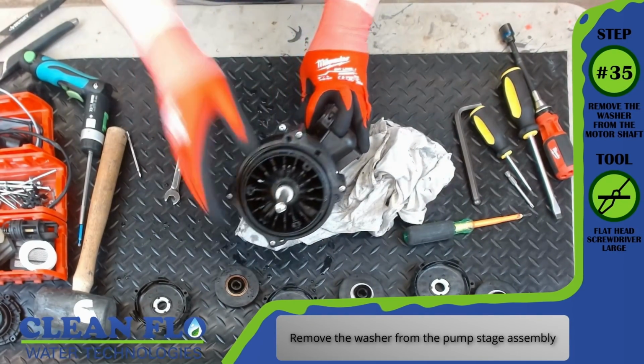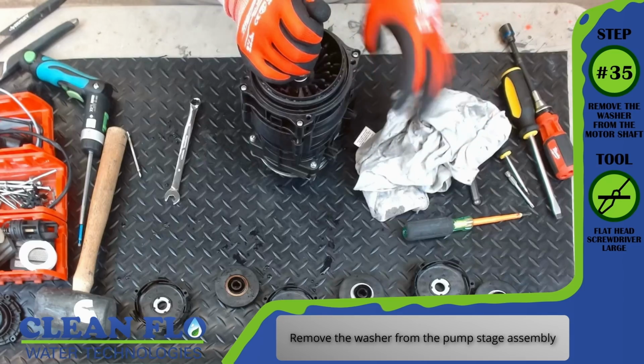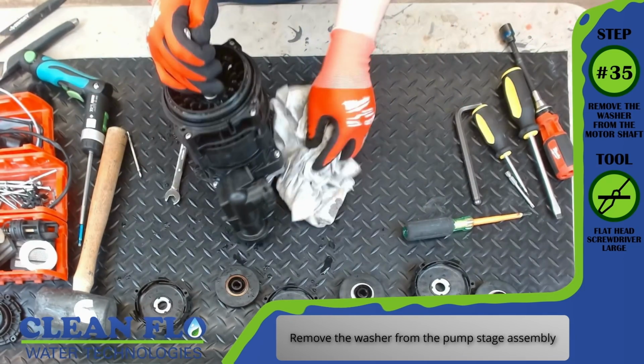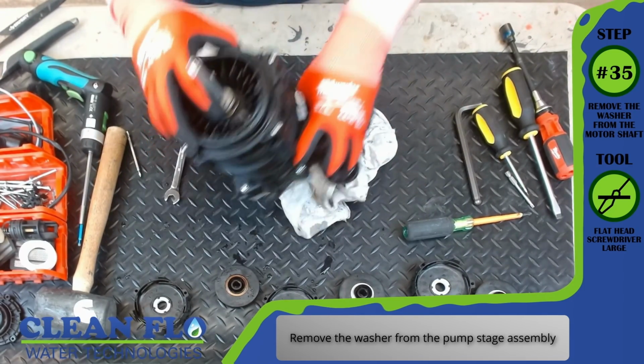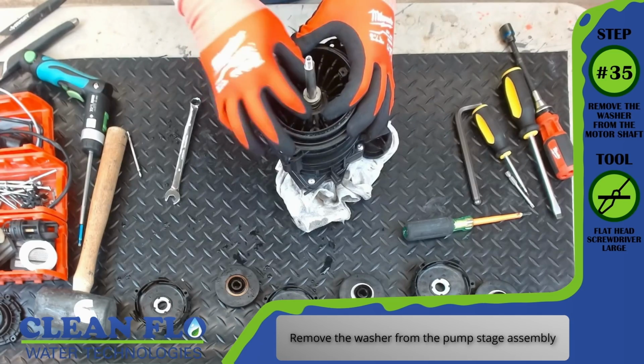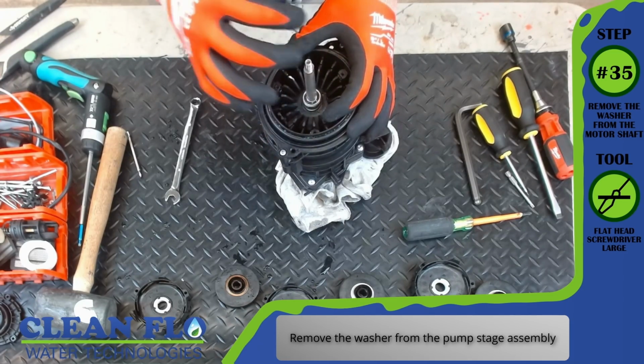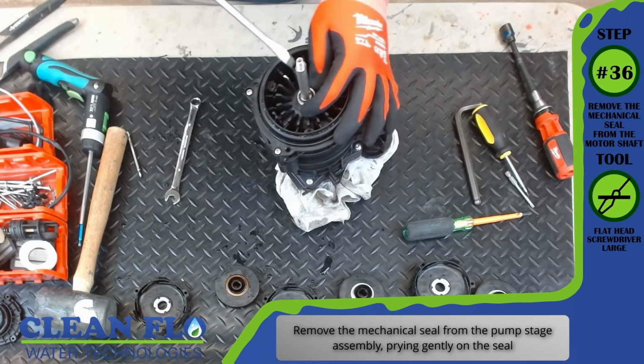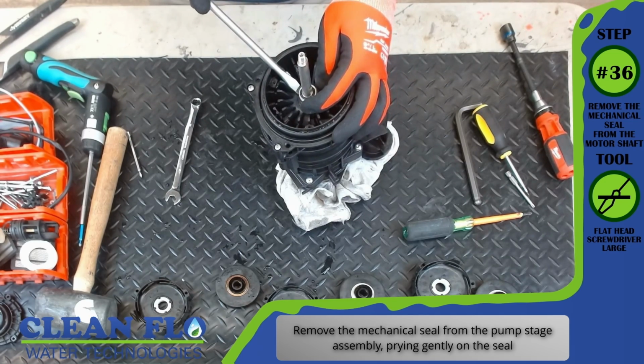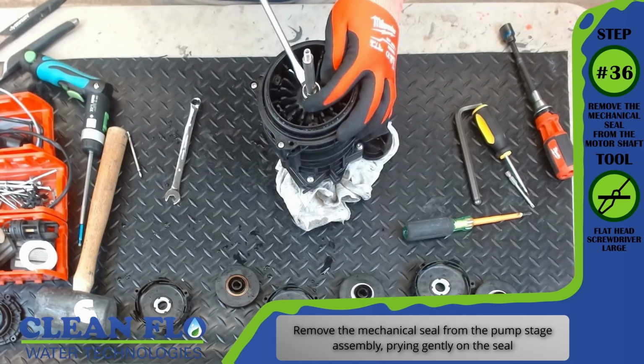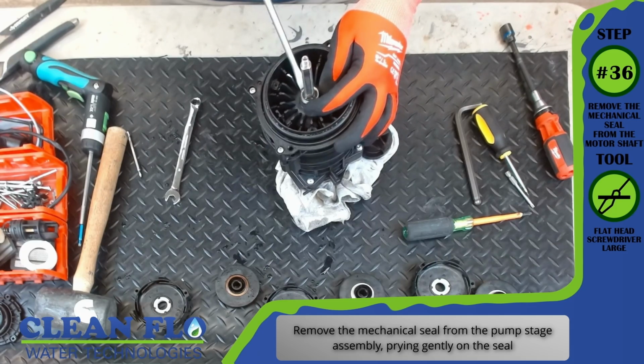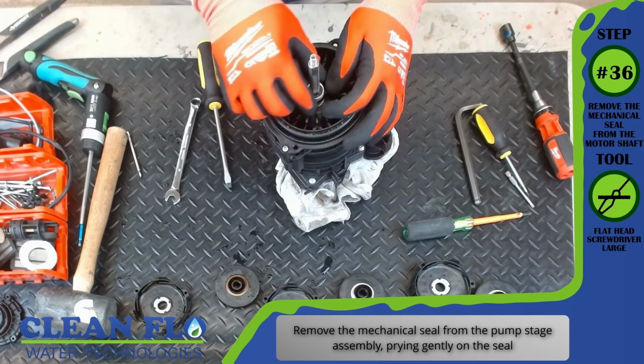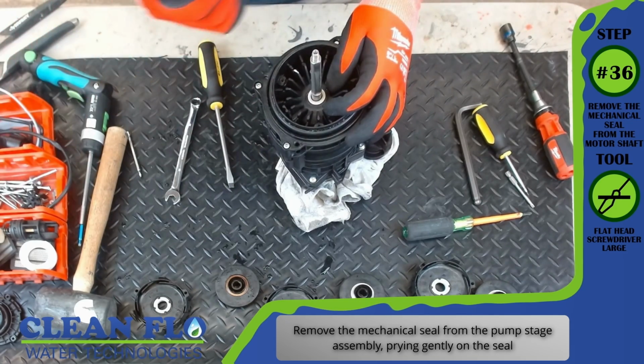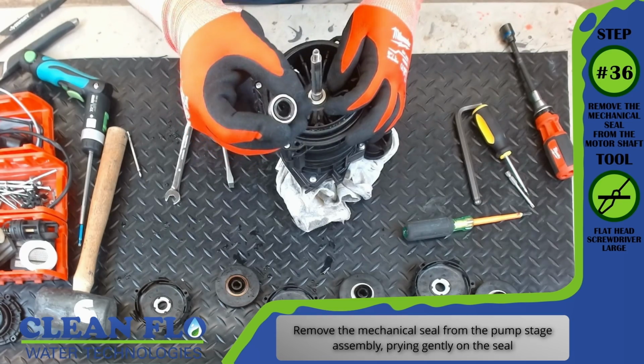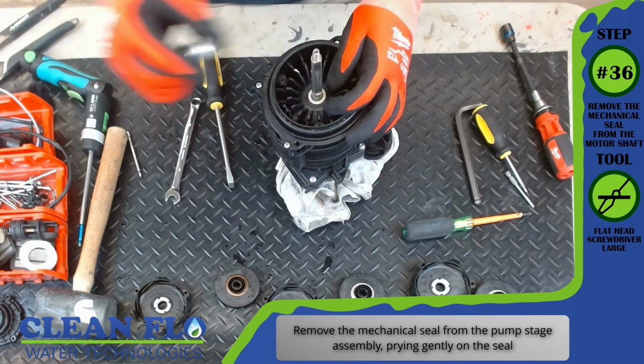Step number 35, remove the washer from the motor shaft. Tool, flathead screwdriver. Remove the washer from the pump stage assembly. Step number 36, remove the mechanical seal from the motor shaft assembly. Tool required is a large flathead screwdriver. Remove the mechanical seal from the pump stage assembly, prying gently on the seal.